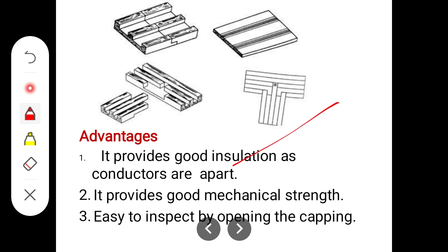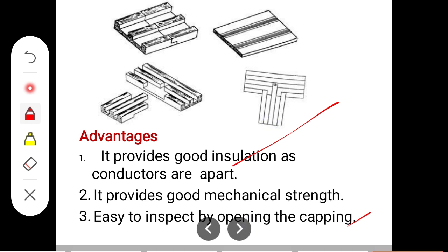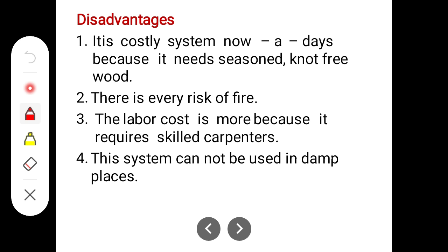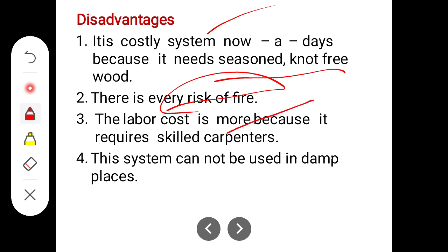So it provides good insulation as conductors are apart, and good mechanical strength, and it is easy to inspect by opening the capping. But this requires skilled persons. The disadvantage is that it is a costly system nowadays because it needs seasoned, knot free wood, and there would be a risk of fire. Labor costs are high because skilled labor or carpenters are required. So this system cannot be used for damp places.